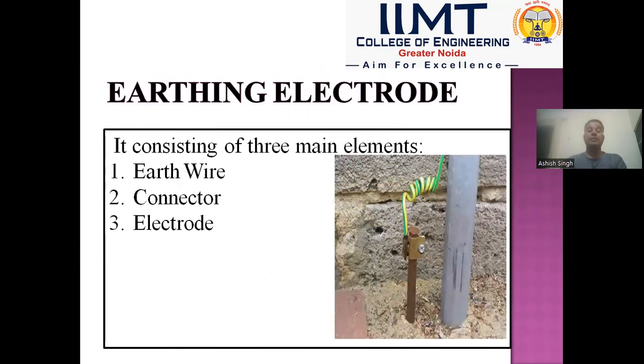another class. So earthing mainly consists of three components. First one is the earth wire that connects the non-current carrying metallic part of appliances to the earth electrode. Second one is the connector that connects the earth wire tightly to the electrode, and third one is the electrode that is used to discharge leakage current to the ground.